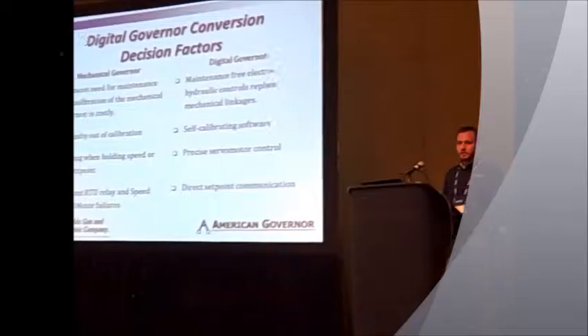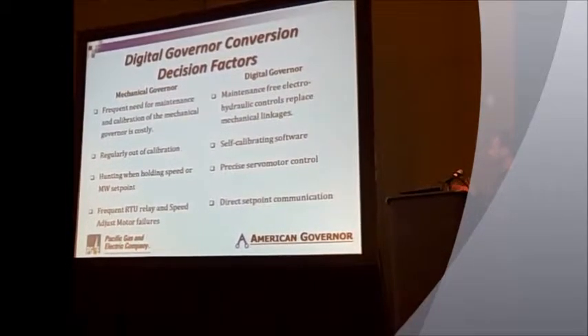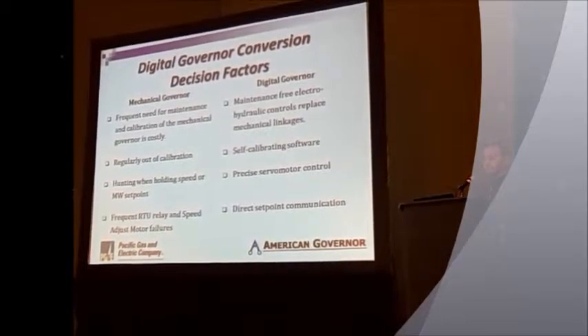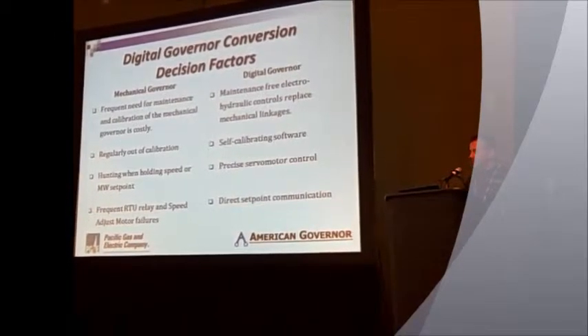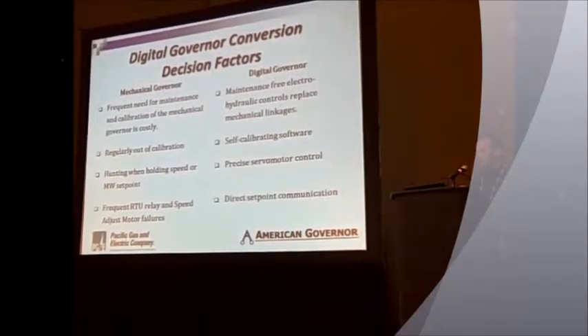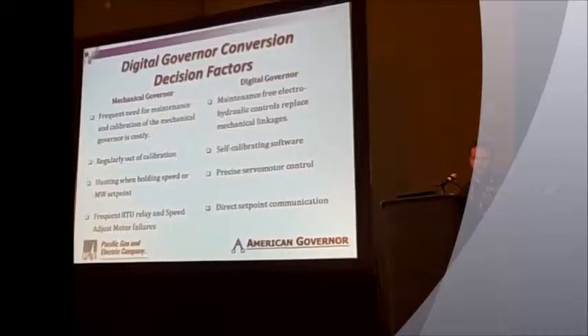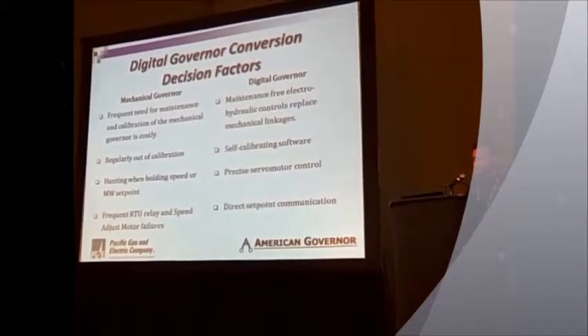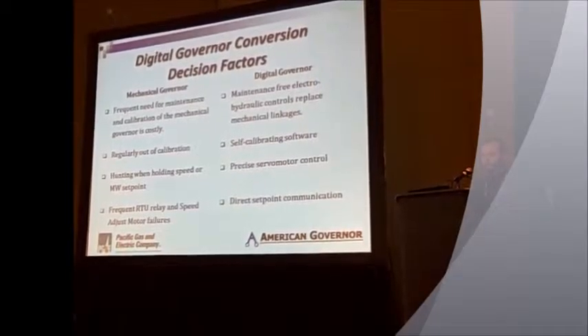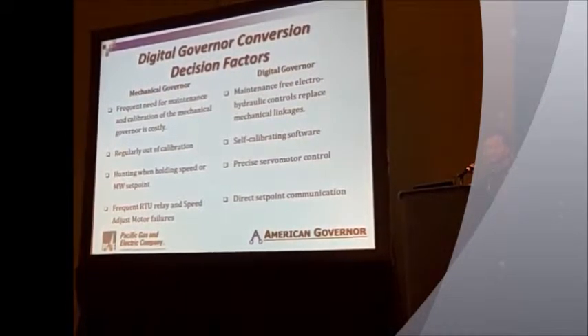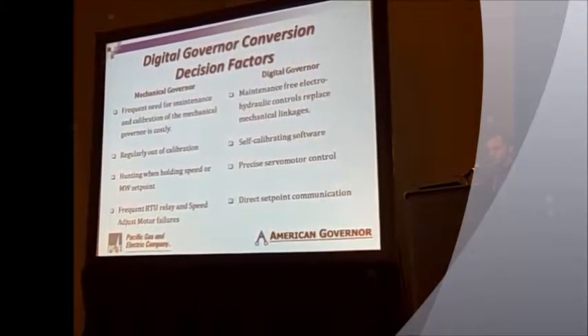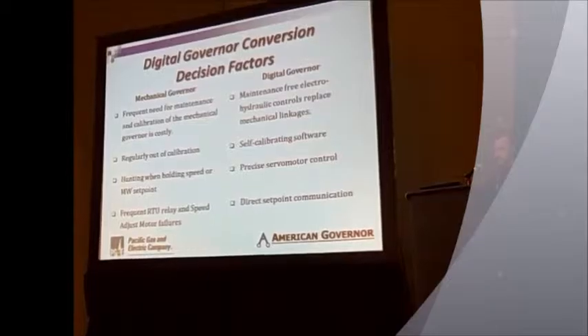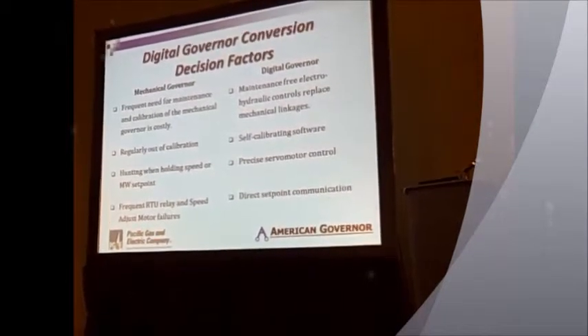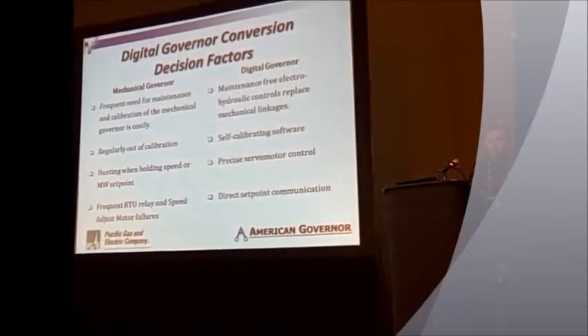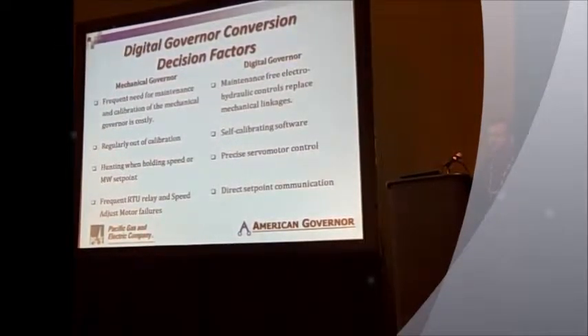So in, I believe, 2008 through 2009, we engineered and installed this system, and I'll talk a little bit about what components were in the system and what the gains were. So the biggest advantages of the digital conversion are the replacement of the 450 feet of cable and 2 tons of weight with modern electro-hydraulic controls. This allows for precise servo motor control, allows for servo motor control to be self-calibrated by the software, and additionally, we're going to have direct set point communication from the California ISO to the governor, and get rid of that several step communication link with analog signals and set point raise and lower commands.